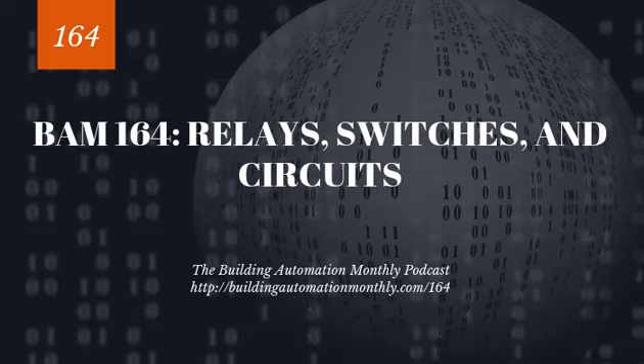So you've got this electrical signal from this transformer, maybe 120 volts, coming into the normally open contacts and leaving the normally open contacts of that relay. When you turn on your fan command in your building automation controller, that then energizes the coil, which causes that normally open set of contacts to close. And now that completes a circuit which allows that fan starter to turn on, or that electric heat to turn on.